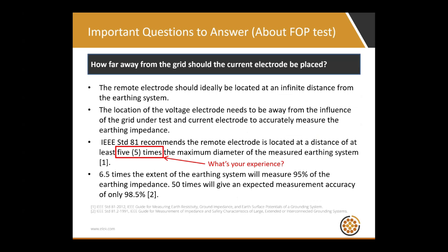Let's talk about some important considerations of the fall of potential test itself. For example, how far away from the grid should the current injection electrode be? There are simple rules. Ideally, it should be located at an infinite distance away. That's not practical. There are a couple of rules of thumb mentioned in IEEE 81 and IEEE 80, suggesting that you should locate the current injection point at least 5 times the diagonal distance of your grid.